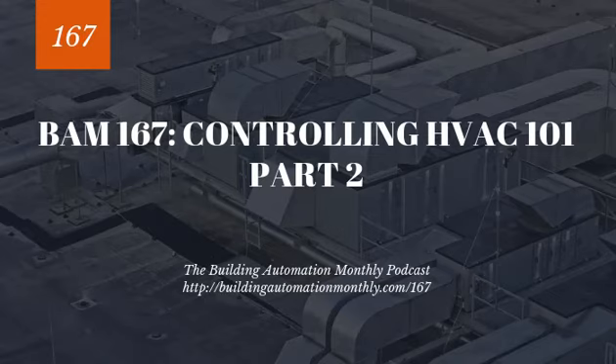So then dampers. As I mentioned, there's primarily two types of dampers. There's proportionally offset dampers that I just went through, right? That's your outdoor air and your return air dampers. As long as they're not slipping and the linkage isn't messed up, they should be fine. You rarely should damage your system with proportionally offset dampers. Open and closed dampers are the primary area you need to focus on and be careful with.